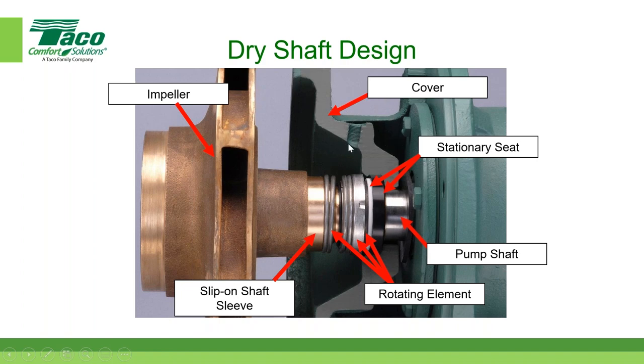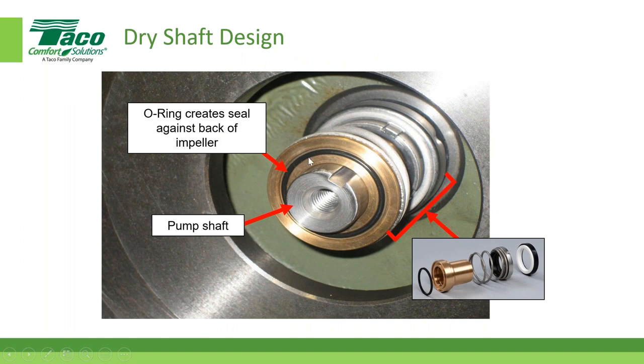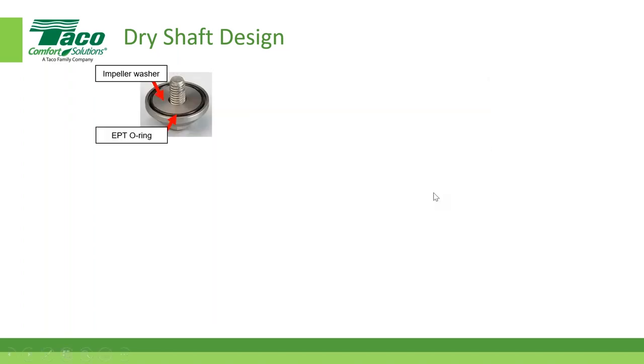You can see one of our tappings for possibly a pressure gauge. And there's that slip-on shaft sleeve, and there's your impeller. So that's that dry shaft design. This O-ring creates a seal against the back of the impeller. So the impeller pops right in against that. And that pump shaft mounts there as well, and that seal sits there. So the impeller washer has an O-ring as well.